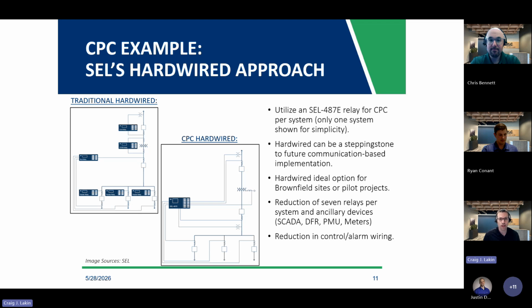Another great feature is that it addresses the difficult situation of the brownfield, as Ryan was alluding to. This could potentially be a great application for a brownfield application, and maybe it's not a full-blown CPC example as I'm showing here, but maybe I want to implement it simply on the feeder protection, and I'm just going to do a centralized protection on just the feeders, leaving the transformer alone or leaving the line protection alone. So again, a great opportunity for greenfield, good opportunity for brownfield.